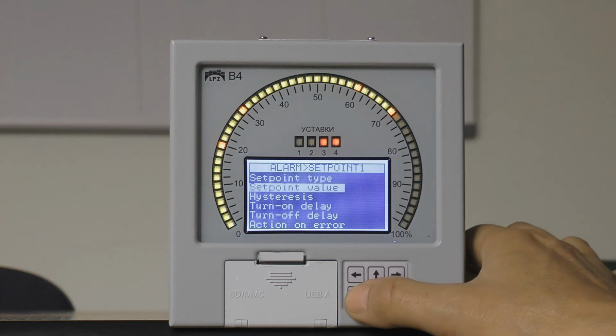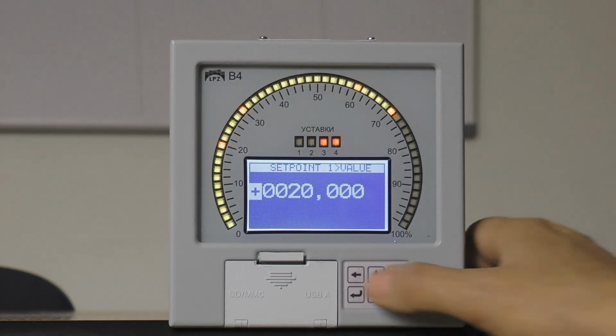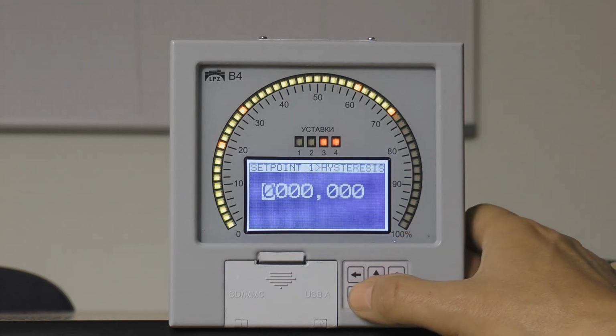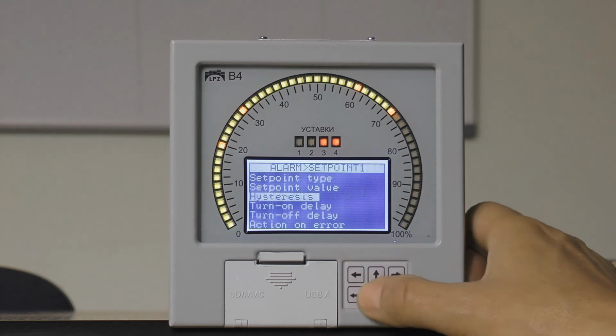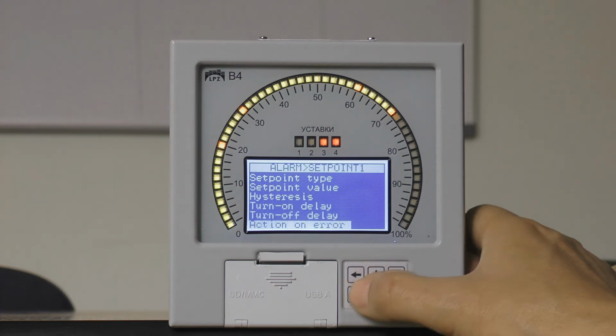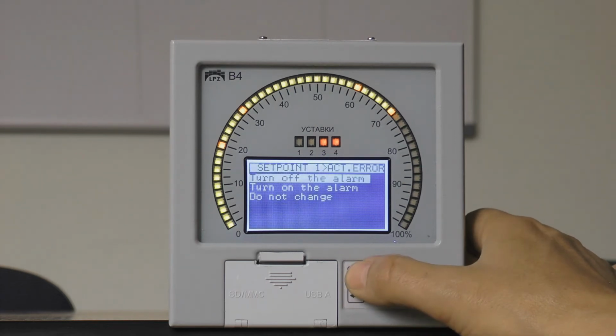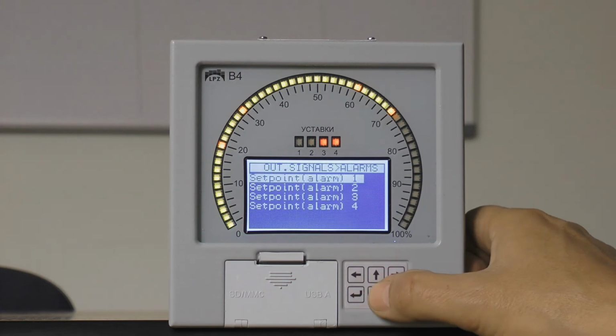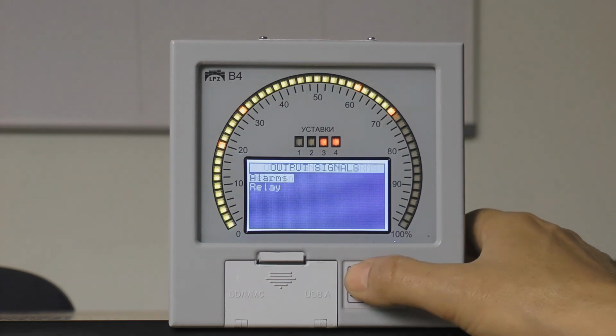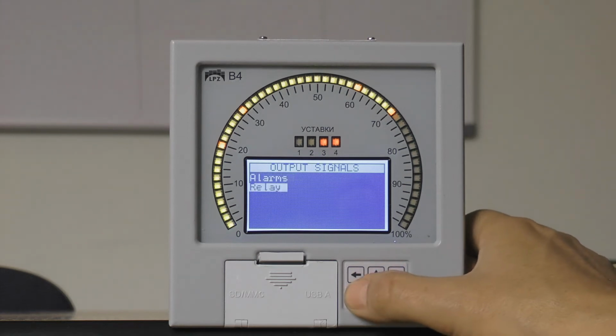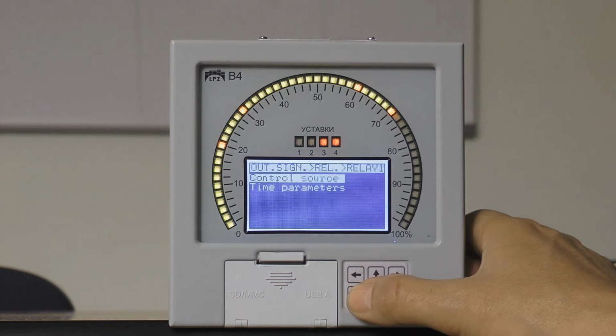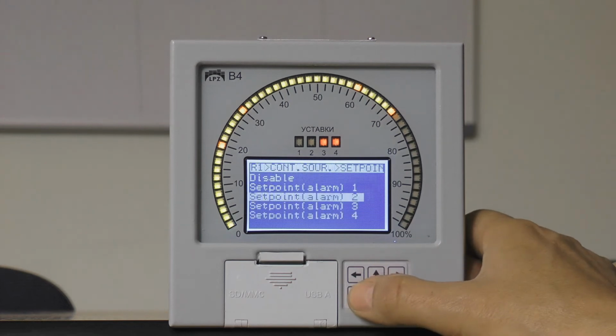The first set point we are considering is adjusted at 20% of the scale. The hysteresis is 0. We skipped some of the items now, and there is action on errors. Parameters of each set point are adjusted in the same way. For each relay, you adjust the set point at which it should close contacts. For example, relay number 1 is connected to a set point number 2. There are other settings which we aren't interested in at the moment.